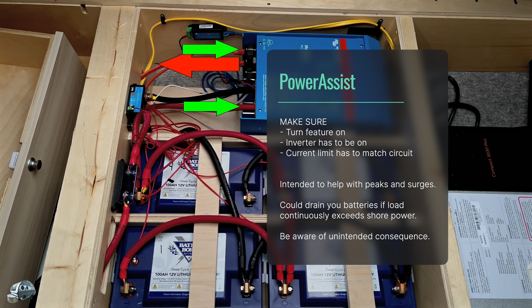If the input current limit is not set correctly, the Multiplus may attempt to draw more current than the shore power connection can supply. An upstream circuit breaker would break the shore power circuit, and the inverter would take over. This is no longer a temporary power assist scenario. Instead of the batteries taking a small hit, the system would draw down the batteries. If the inverter is not set to be on, power assist will not work. An appliance that would otherwise trigger the power assist mode would simply fail to work properly, or all of the 120-volt appliances could falter once the current limit is reached. All of this to say, we like power assist. We will just make sure that all of our settings are correct, so power assist is what we actually get.